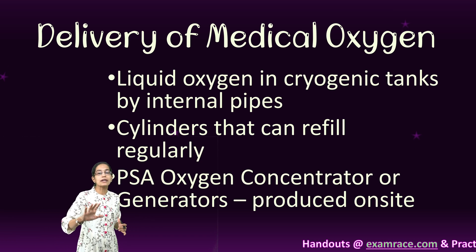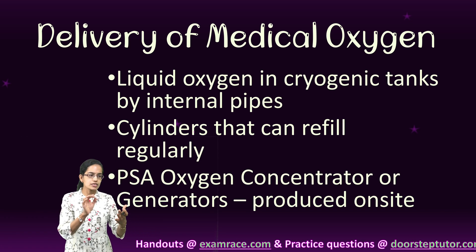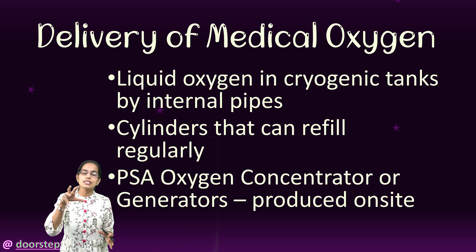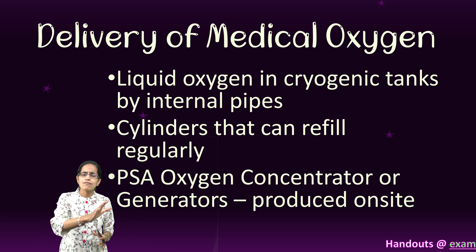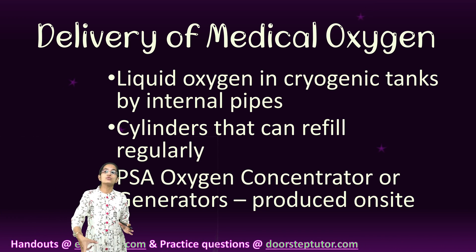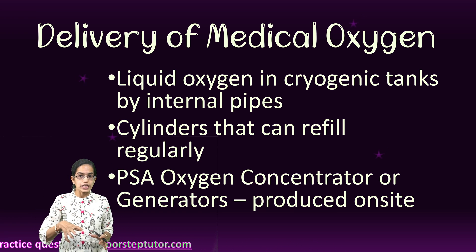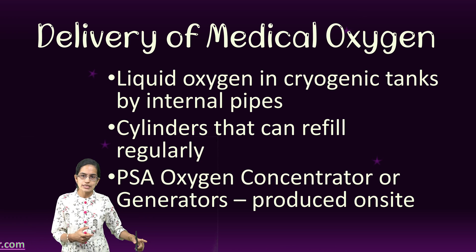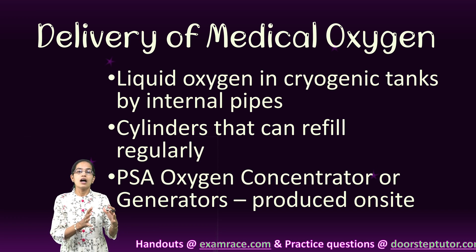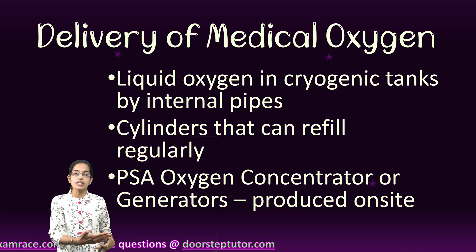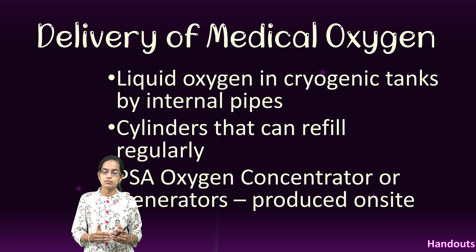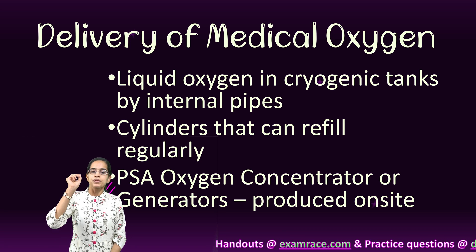The third important development is PSA — Pressure Swing Adsorption — oxygen concentrators, also called oxygen generators. These machines were introduced in the 1970s and have been widely in circulation in parts of North America, Europe, Africa, and Asia. The key idea is that oxygen is produced on site, so there is no requirement for storage. PSA oxygen concentrators are highly portable, can be utilized to their best capacity, and oxygen can be generated whenever required.